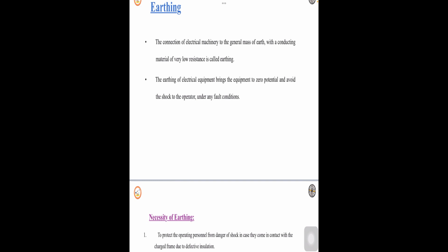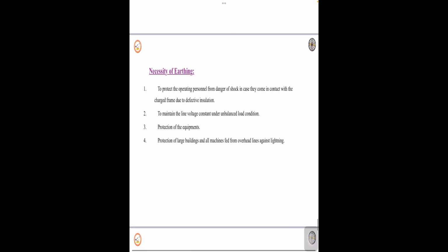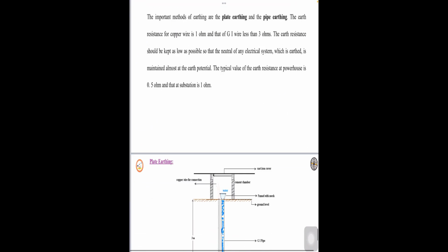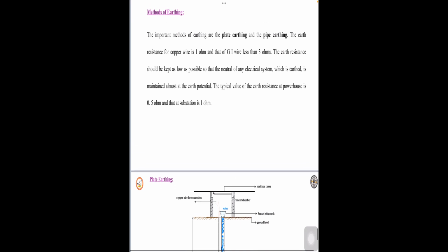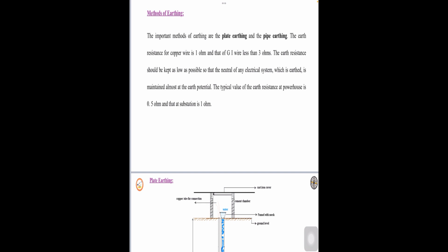Now when it comes to types of earthing, there are different types like rod earthing, pipe earthing and plate earthing. Let us understand plate and pipe earthing as they are very important. Here the earth resistance of copper wire is generally 1 ohm and that of GI wire is kept at less than 3 ohms. As much as possible the earth resistance should be low so that the neutral of the electrical system which is earthed is maintained almost at earth potential itself. The typical value of earth resistance at a powerhouse is 0.5 ohms and at a substation it is 1 ohm.